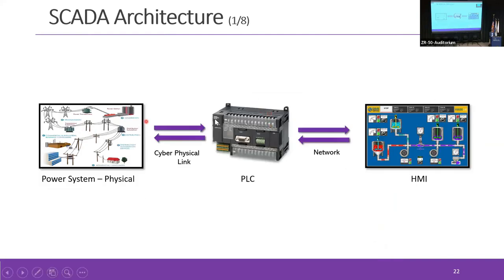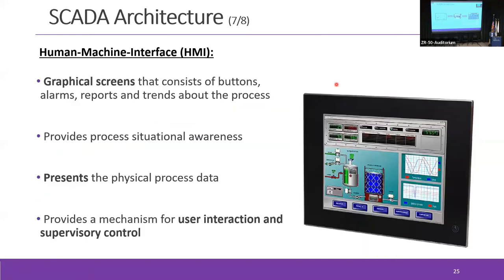The PLC takes the sensor readings, runs a program, and gives control actions, but it also passes these sensor readings to the human machine interface, which shows the operator the current status of the system. It also allows the operator to override the PLC and take specific control actions—for example, regardless of the PLC, disconnecting a load by giving a command through the HMI to open a specific switch. All of this exchange happens through the network connecting the PLC to the HMI.